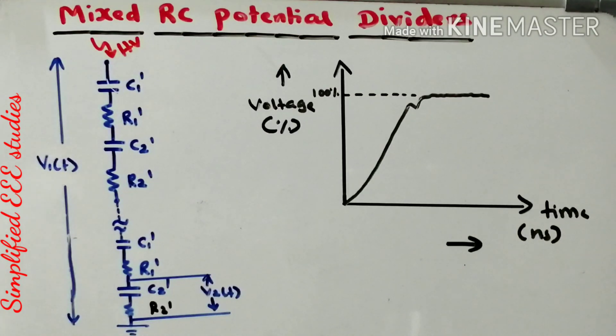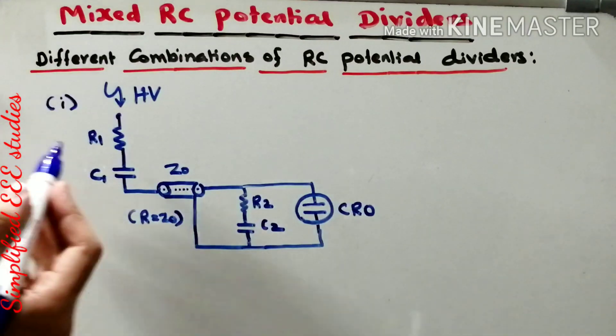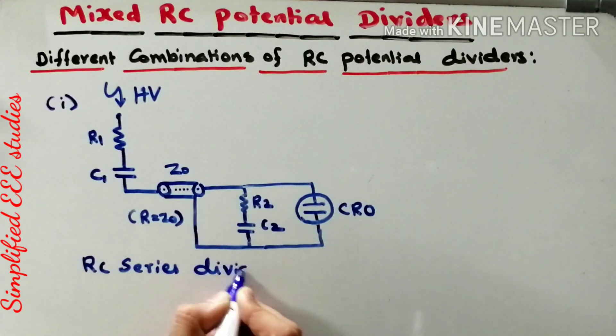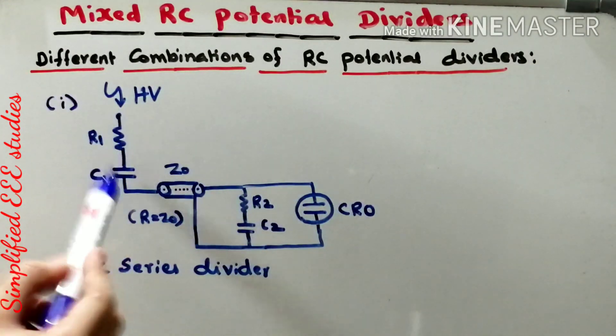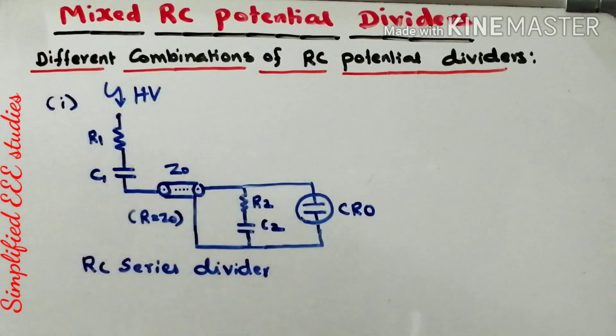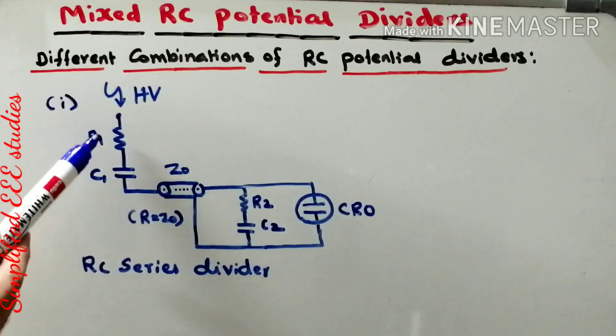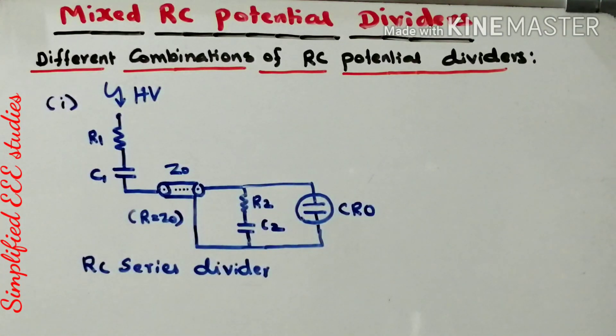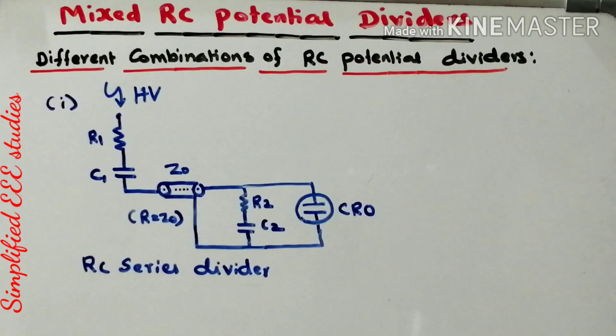There are different combinations available: you can connect RC elements in series, shunt, or series-parallel. The first combination is known as RC Series Divider. It has two arms — R1C1 as the high voltage arm and R2C2 as the low voltage arm. The total high voltage is divided across these arms, and the voltage across the low voltage arm is connected to a CRO. This combination provides a fast response and is the most popular type of RC potential divider.